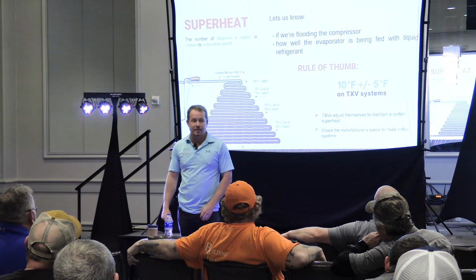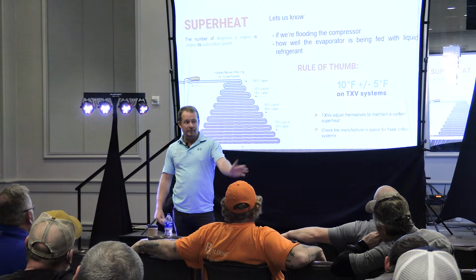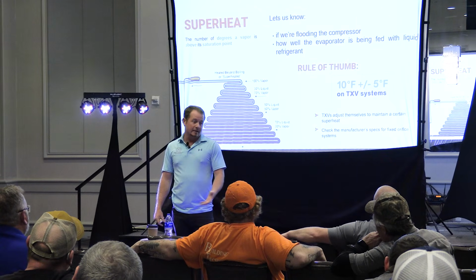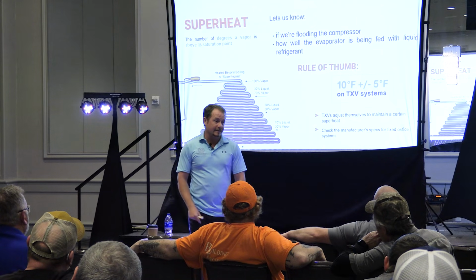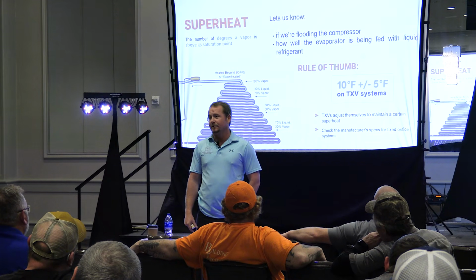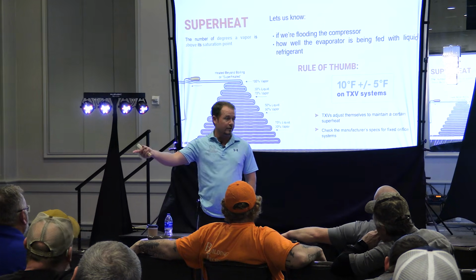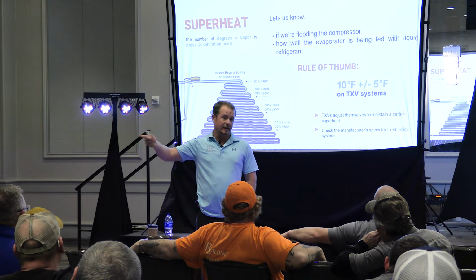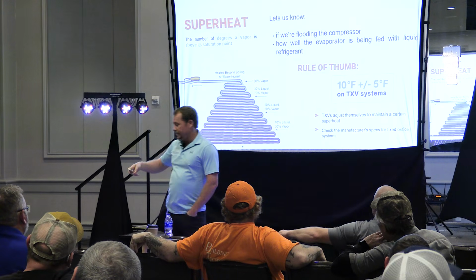So the next question is, are we talking about compressor superheat? Are we talking about evaporator superheat? Because, you know, Copeland says they want 20 degrees of compressor superheat. They want your superheat to be 20 degrees at the compressor. They'll tell you that less than that's actually a problem in many systems. Knowing where is pretty significant.